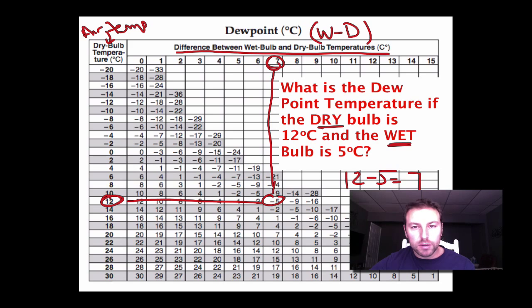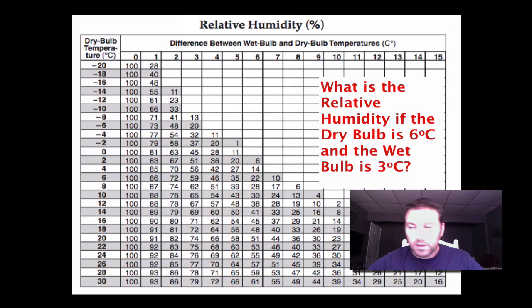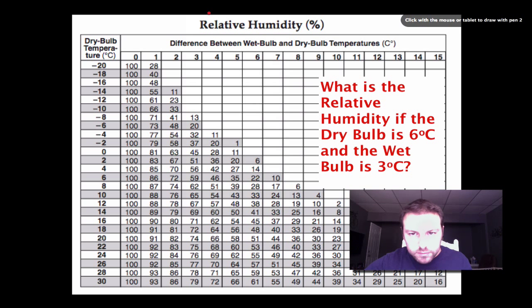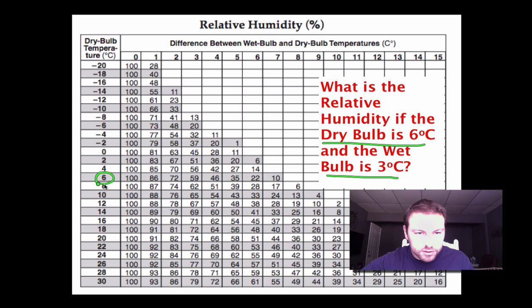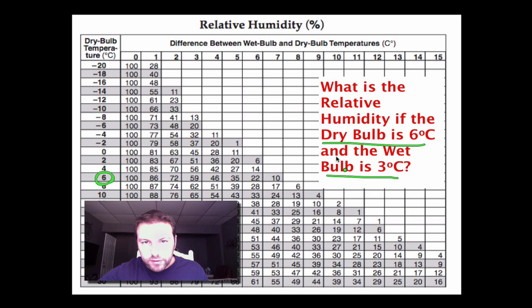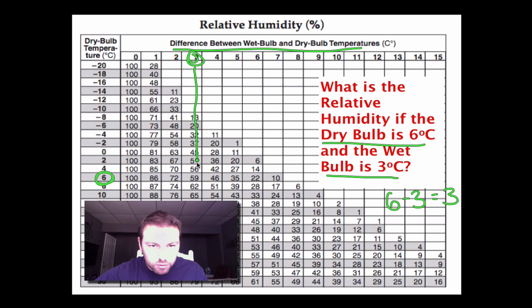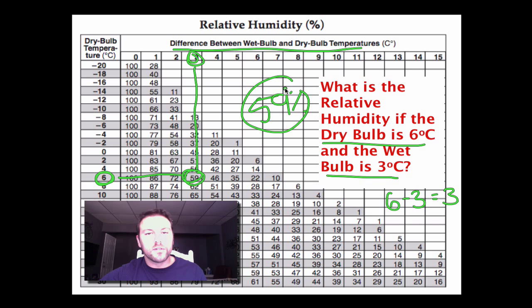We can do the same exact procedure to find relative humidity using the sling psychrometer. We need our dry bulb and wet bulb temperatures. Go to the left side and find the dry bulb temperature of 6 degrees Celsius. Find the difference between the wet and dry bulb: 6 minus 3 equals 3. Find 3 at the top of the chart, move down to where both values meet, and there you go — 59%. Same exact procedure for both dew point and relative humidity.